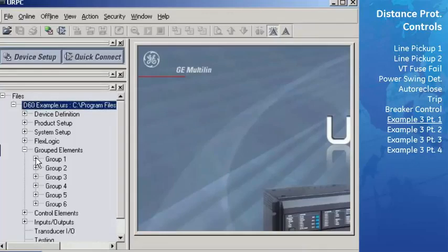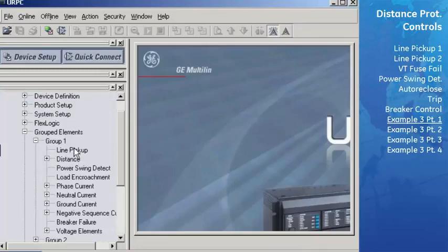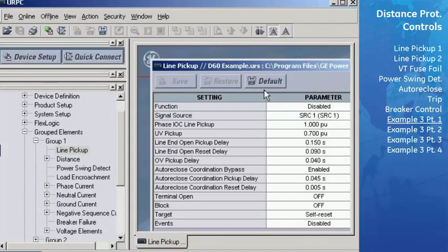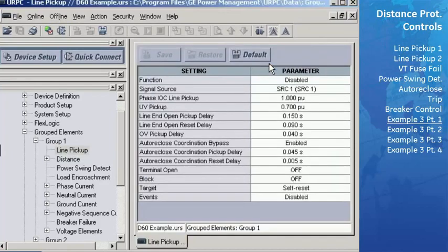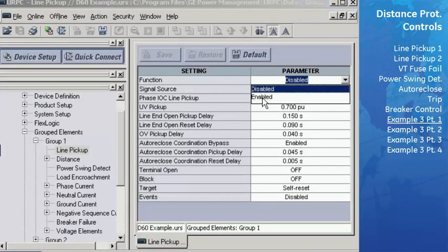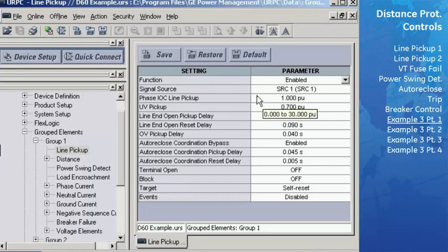In the settings file used previously, open Grouped Elements, Group 1, Line Pickup menu. Set the function field to Enabled to make this element active. Keep the signal source setting as Source 1, which is the same source as the distance elements. Keep the phase instantaneous overcurrent setting at 1 per unit and the undervoltage pickup setting at 0.7 per unit. These are realistic values for a system with a system impedance ratio of less than 30.